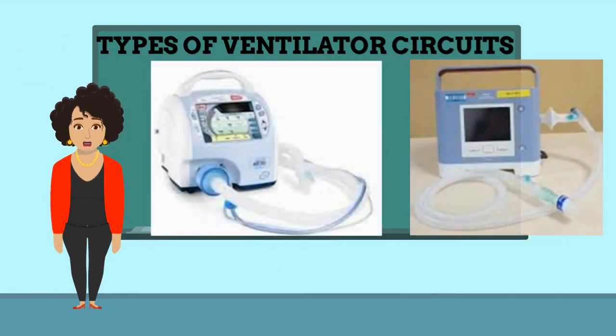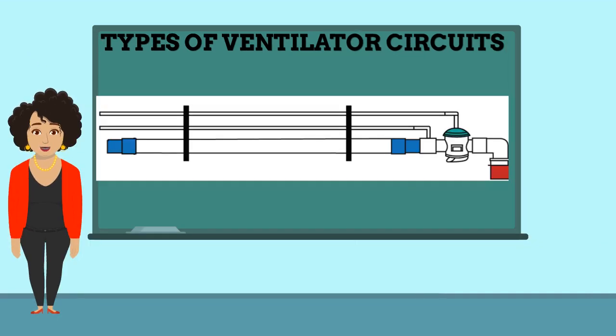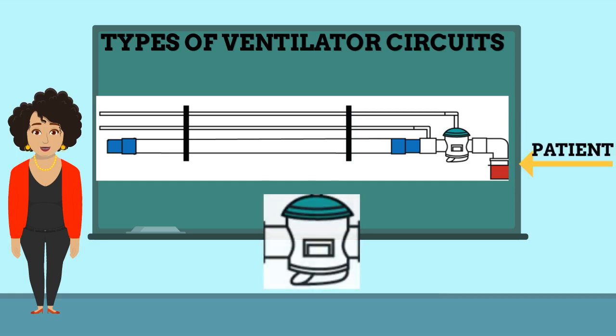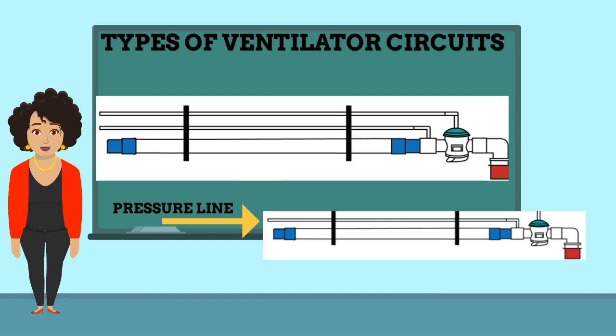You're probably wondering what an active or passive circuit is — don't worry, I have the answer. Typically, an active exhalation valve near the patient is used with portable ventilators. During inspiration, the exhalation valve is closed via the pressure line from the ventilator, and the expired air is directed out of the exhalation valve.